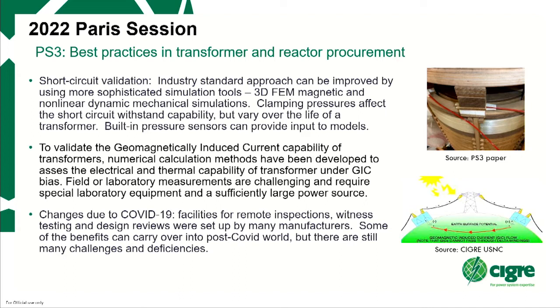Clamping pressures are directly related to the short circuit withstand capability of transformers, but they vary a lot over the life of the transformer. So there's work being done on using built-in pressure sensors that can provide real-time feedback of changes in clamping pressure, and using these as inputs to various models.